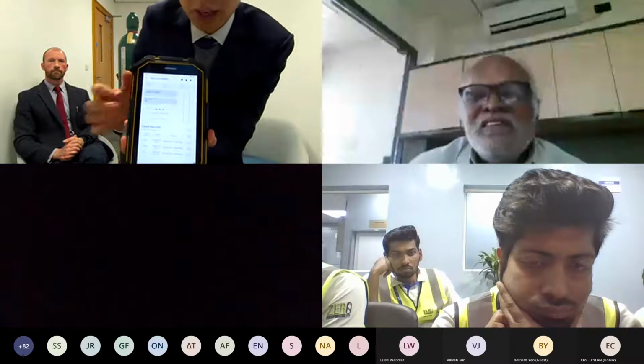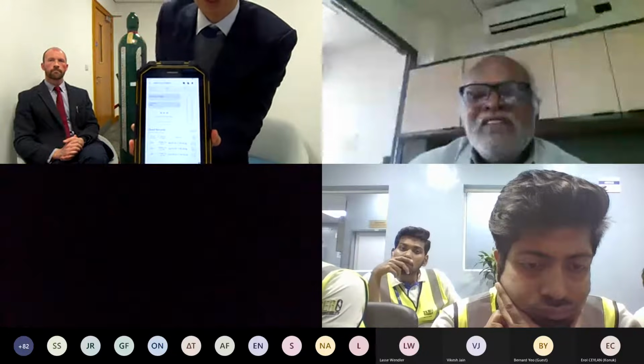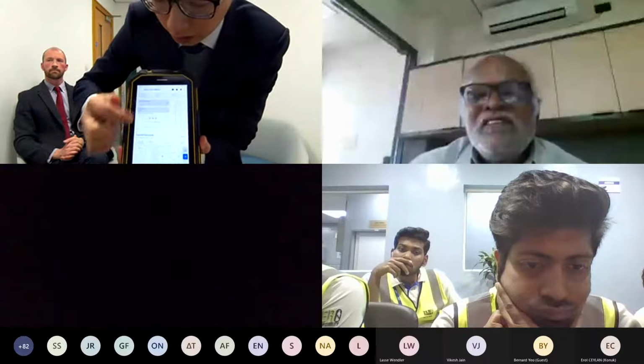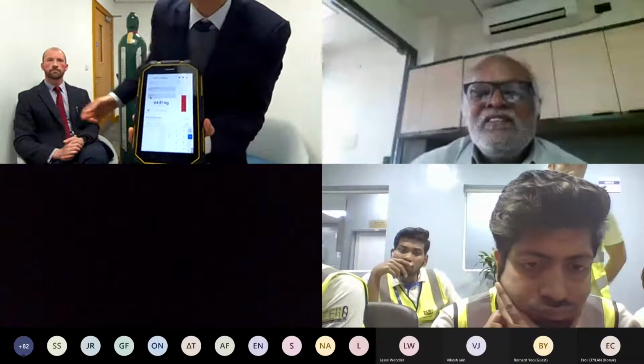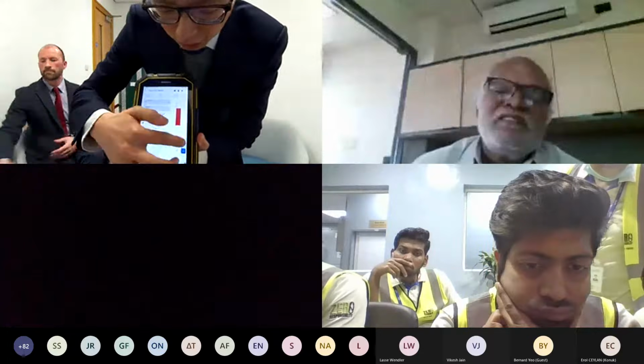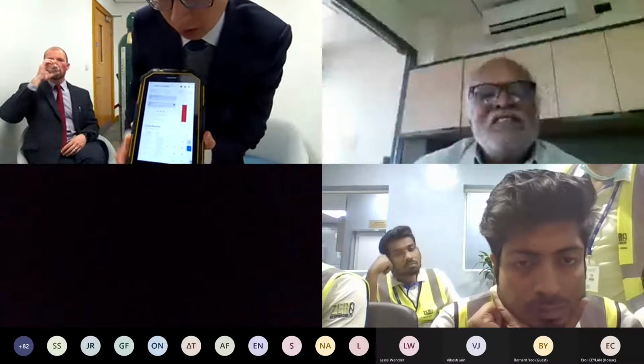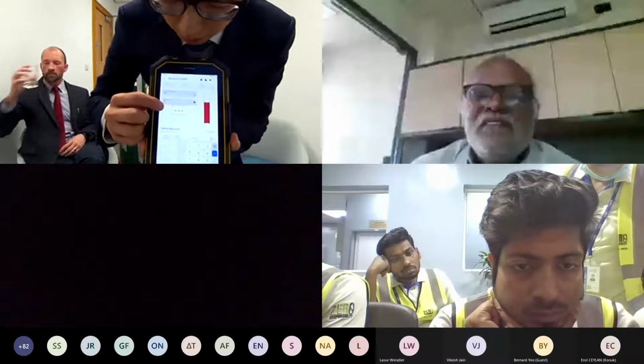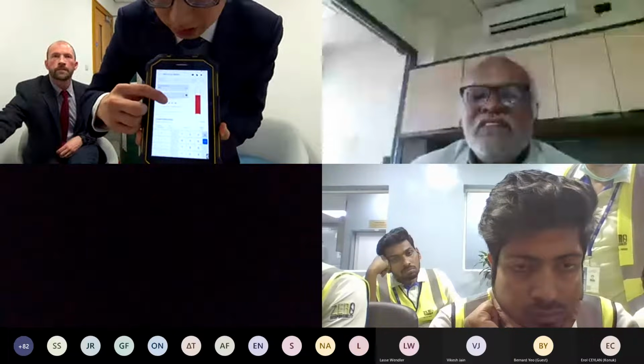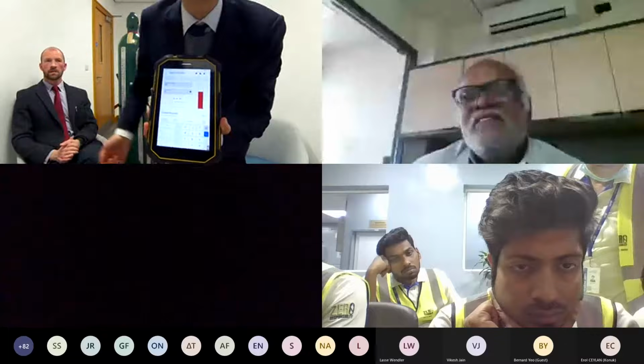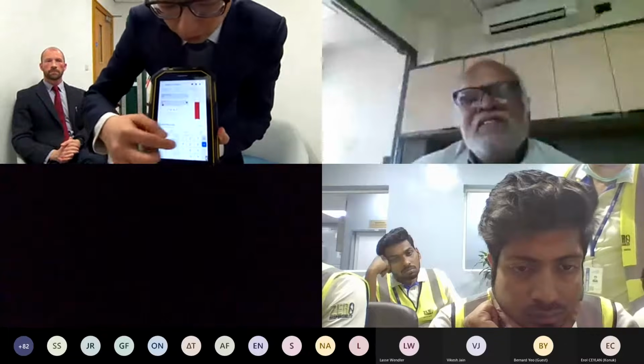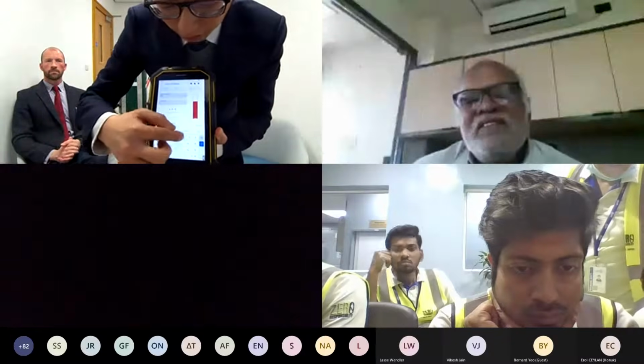For example, if I test my CO2 cylinder and I found the liquid level to be at 100 centimeters, and then I measure the temperature and I realize that the temperature is 31 degrees, or let's say 32 degrees, you will see that there is an error saying must be between 20 and 30. It doesn't allow you to add the record. It doesn't allow you to save the measurement.